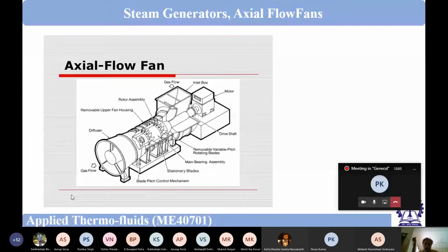And then there will be a duct that will be connected to this. These blades, you see a very large number of blades are there. Quite a few things we have to learn or remember. First thing is that an axial flow machine, whether it is handling a liquid or a gas, has a high flow rate, but the pressure rise generally is small. In an axial flow fan, pressure rise will be small. But that we can compensate.